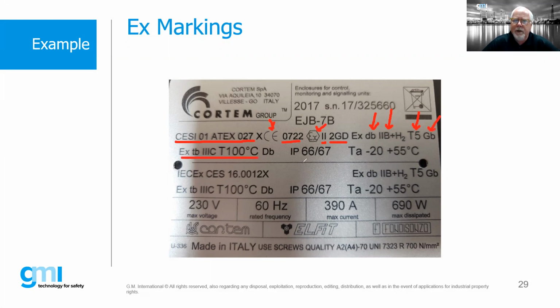So this happens to be our dust marking string, which we won't really cover. Then we have our IP codes. Notice we have both IP66 and 67. And this is important to understand as well. This product is suitable for an environment in which the ambient could range anywhere from -20 to +55. Now, when we look down here, we see there's our IEC EX certificate. This is our IEC EX string, which again is basically the same as what we find here. But under IEC EX, we do not put this information that we see over here. Again, same information for dust, same information for IP codes, same information for T codes or temperature ambience. So in effect, this product is certified both under the ATEX directive as well as IEC EX.